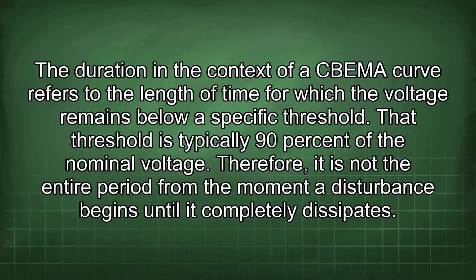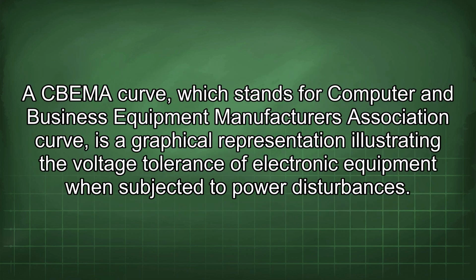Duration in the context of a CBEMA curve refers to the length of time for which the voltage remains below a specific threshold. That threshold is typically 90% of the nominal voltage. Therefore, it is not the entire period from the moment a disturbance begins until it completely dissipates. A CBEMA curve, which stands for Computer and Business Equipment Manufacturers Association curve, is a graphical representation illustrating the voltage tolerance of electronic equipment when subjected to power disturbances.